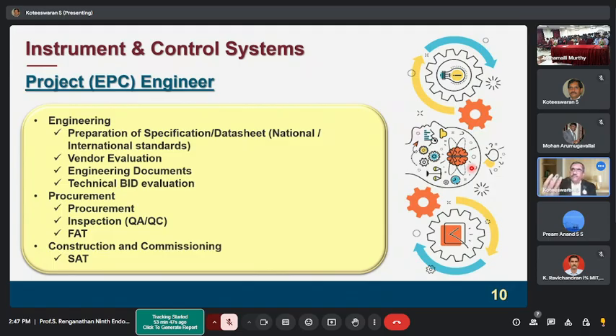So even the design of instruments matters. Take a flow transmitter, for example. Flow is being measured, or it could be any kind of measurement, like an orifice with a DP. That measured mechanical energy needs to be converted to electrical energy, so it needs a transmitter which converts the pressure into an electric signal that is transmitted. When there is a conversion, electronics are involved, and that electronics is installed in the field.